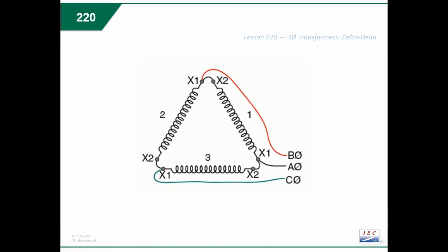I did mention the differences between coil values and line values. So again, as I said, if I took a voltage reading from A to B, that's a line voltage. Okay, don't think of like GFI's line and load. This is line, meaning like electrical lines. So when we're talking about transformer readings, line values, line voltage is A to B, A to C. Coil voltage is X1 to X2.